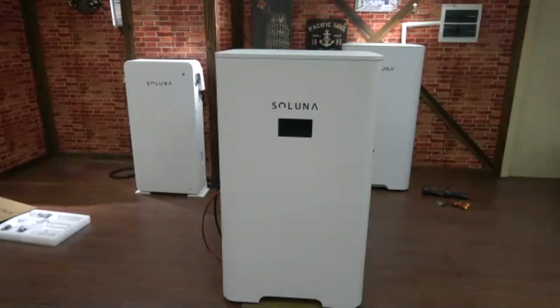And in any kind of switching that takes place, do you have any idea how many milliseconds of transfer time the system is designed for? Right now, our system is designed for 10 seconds, at 1.5 times nominal power. Like this one, this system is S8, it has a 6 kilowatt inverter inside, meaning we can support about 9 kilowatt for 10 seconds.